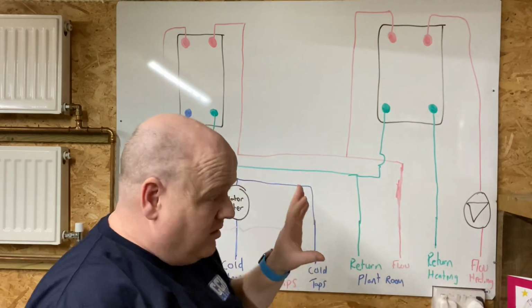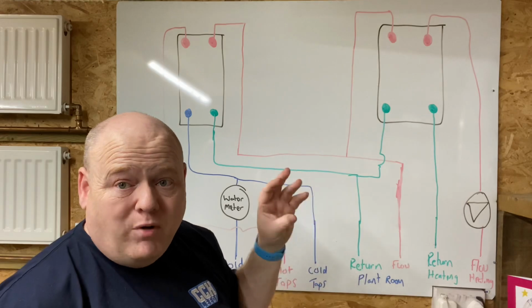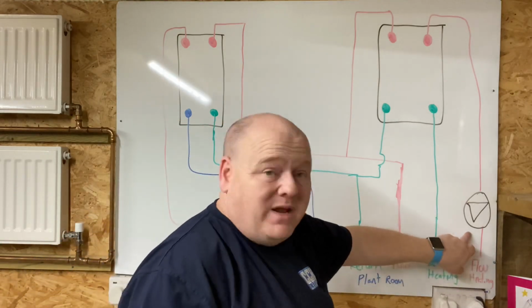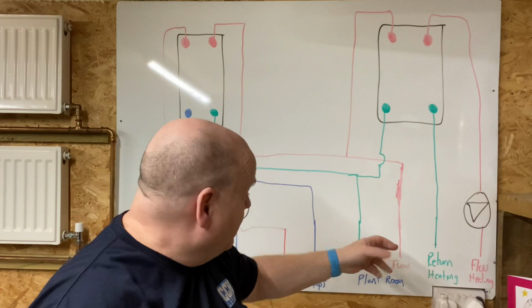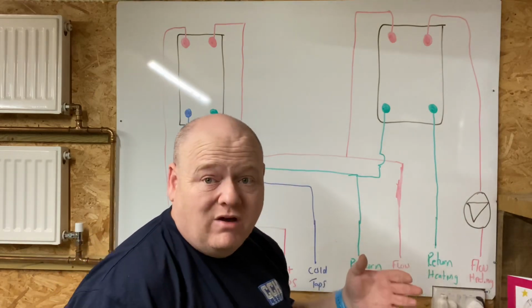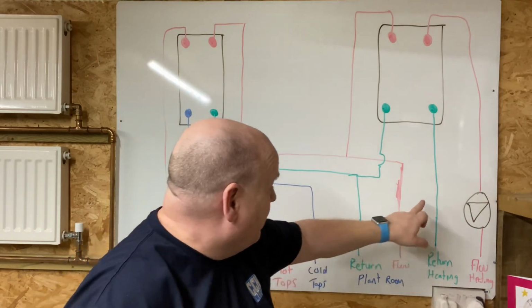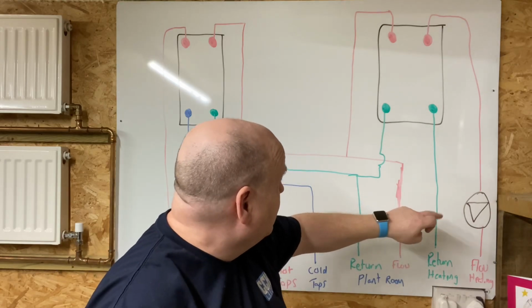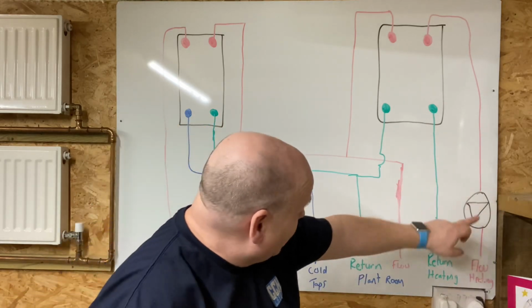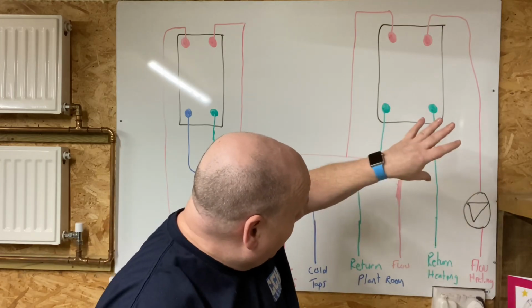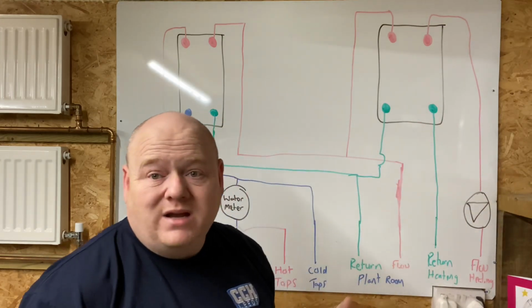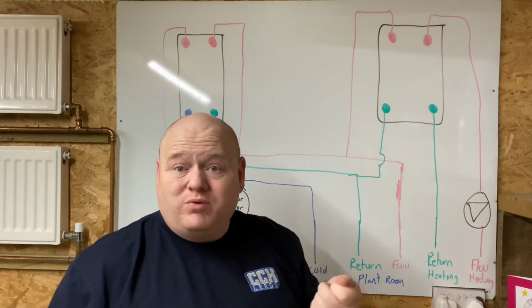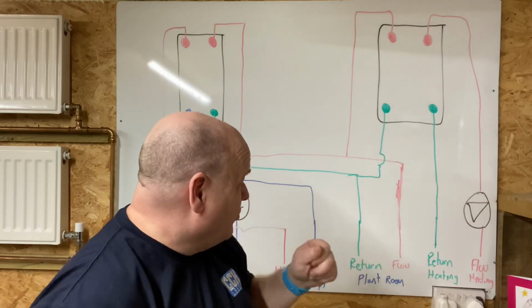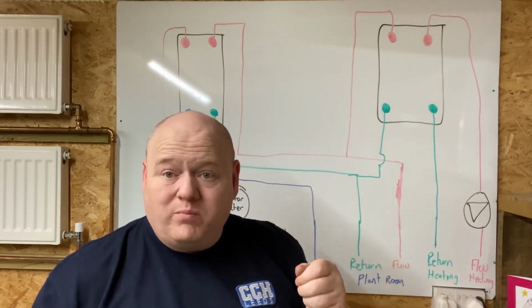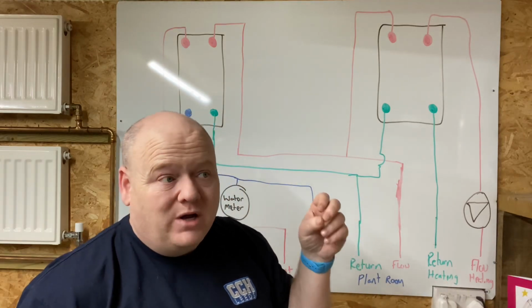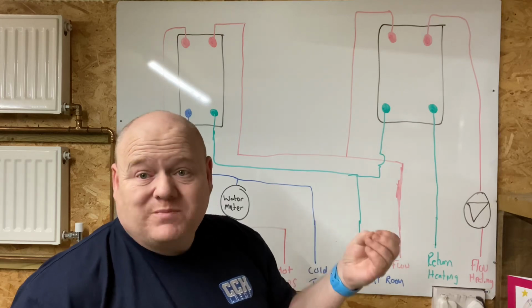On this particular boiler, it seems like the pump was on the flow. It may be that on some systems it might be on the return, so maybe you could have a pump on there. Obviously in boilers, usually the pump will be on the return in the boiler here. So I hope you can understand that part of it now. On this side of it, we then need to put the pressure up. So we need to top it up, and we need an expansion vessel.